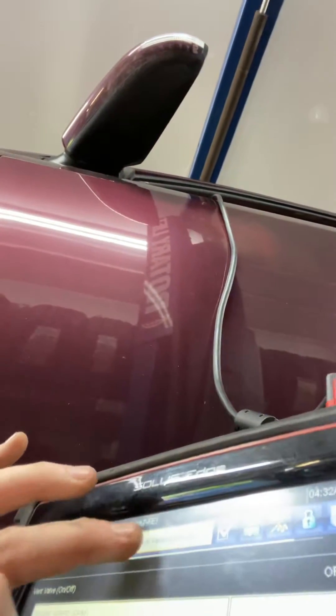We're going to take bi-directional control of the vent valve. Before we roll over, I'll show you — we've got a vent valve clearly in flow. We're going to swoop over here and turn the vent valve off. We've already verified what they call the purge as a variable switching valve. The issue being that valve is basically still seeping and not sealing.